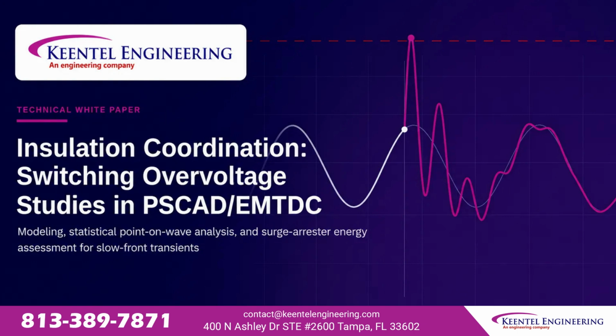Every time a breaker or switch operates on a high-voltage transmission system, it launches traveling waves down the line, exciting the network's inductance and capacitance into oscillation. On long, extra-high voltage lines, the resulting switching overvoltage is among the most demanding events the insulation will ever see.